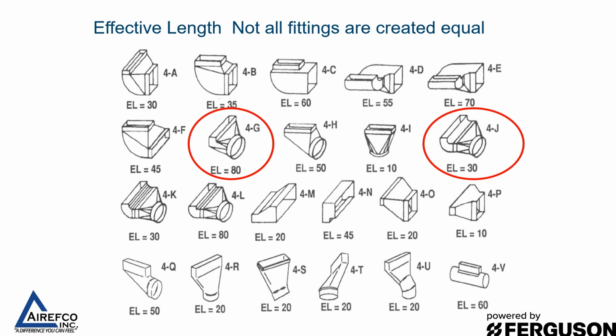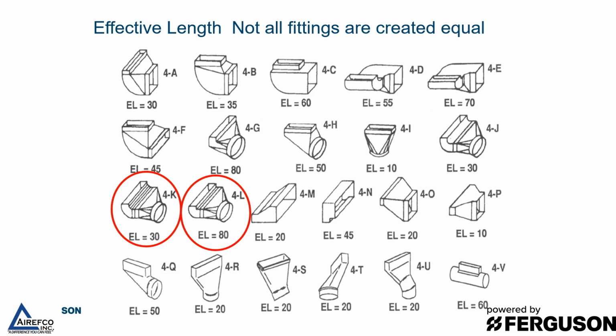Manual J has a number of pages that show you the different equivalent lengths for different fittings, and you'll notice that not all fittings are created equal. The 4G fitting has an equivalent length of 80 feet. A similar fitting, the 4J, has an equivalent length of 30 feet. Also, the 4L fitting has an equivalent length of 80 feet, and a similar fitting, the 4K, has an equivalent length of 30 feet. So when considering fittings for your job, you need to take into consideration the effective length of each fitting and what it's going to add to your duct run.